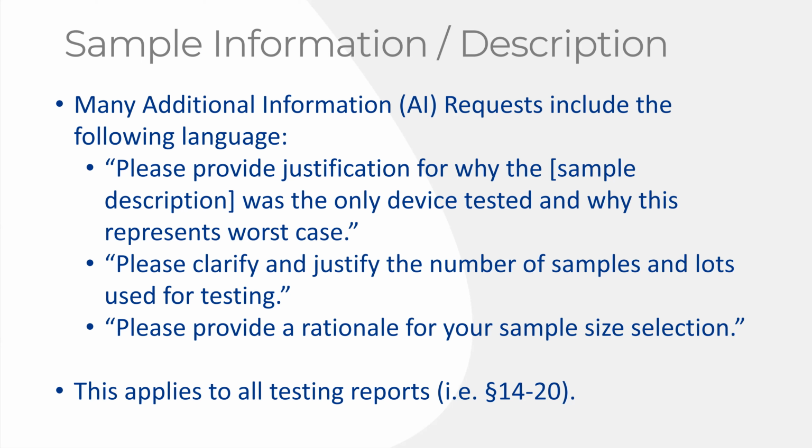But the problem I run into is they didn't put in any justification for sample size. They didn't put any picture of what was used for the samples. They didn't write down the lot information sometimes. They didn't identify what is the worst case scenario for the samples. All that information is left out. Do not do that.